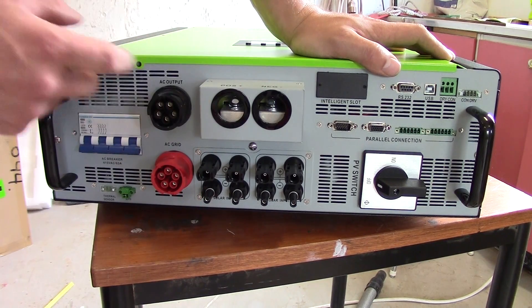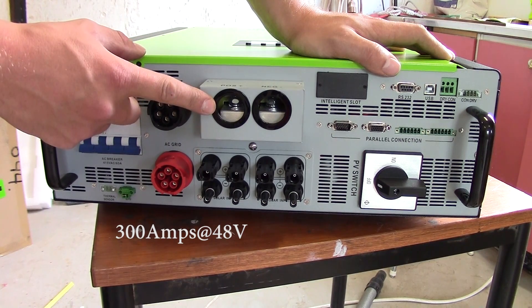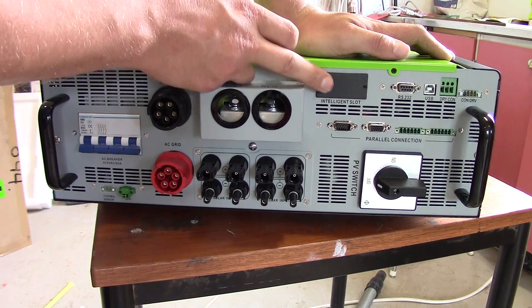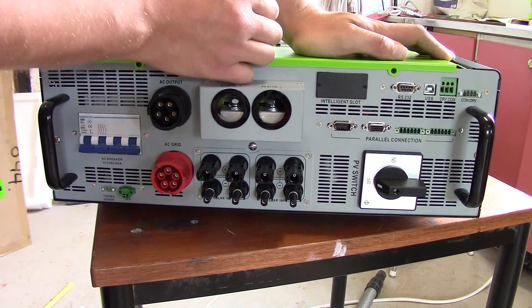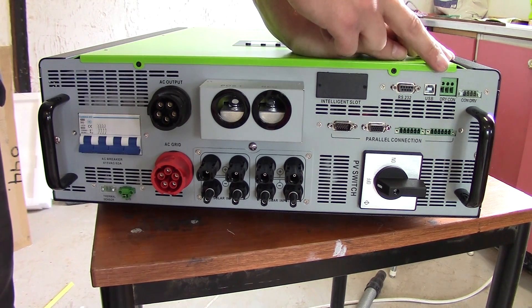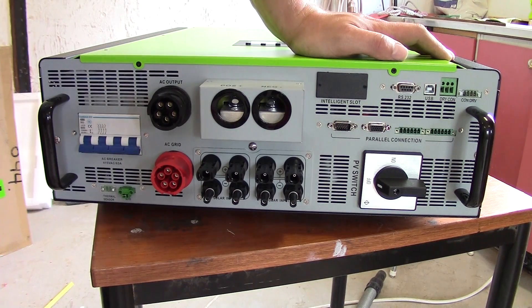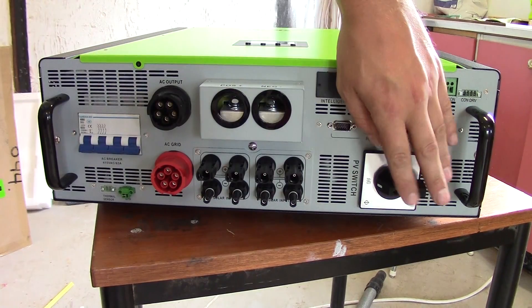The battery connection here should use very, very thick cables, as it should be able to handle almost 300 amps. There's an intelligent slot — that's where I'm going to connect my Modbus card, so I'm going to remove that and install it. There's a parallel connection to connect up several units. RS232 and USB are to connect it to the computer. Dry contact — that's a utility connector where you can connect stuff to be able to start the generator and things like that. And then of course you have the PV switch.